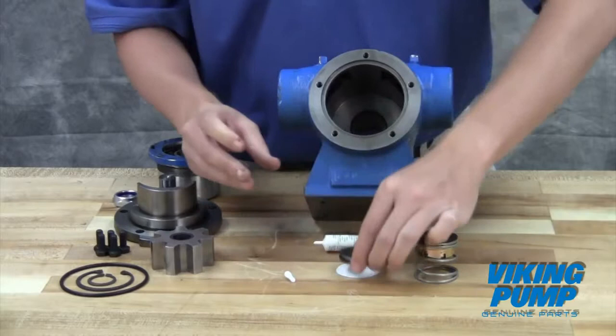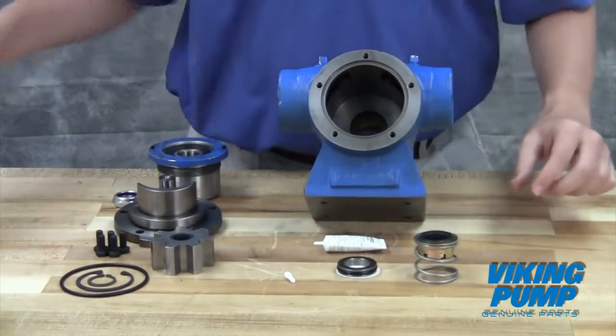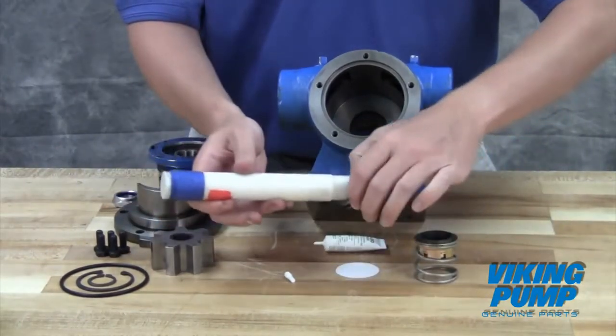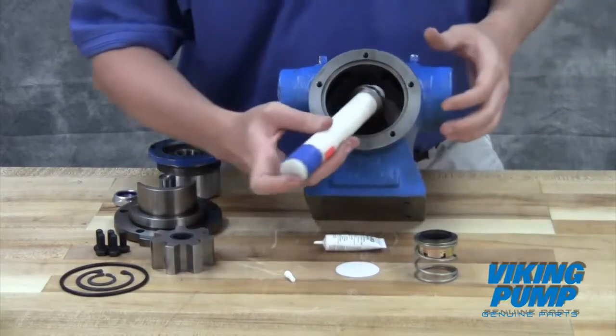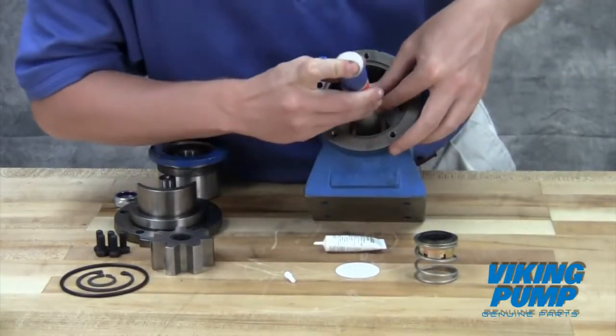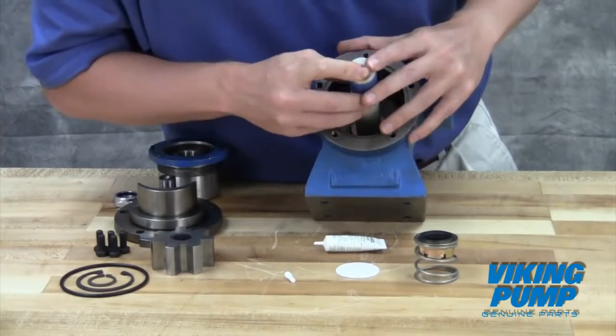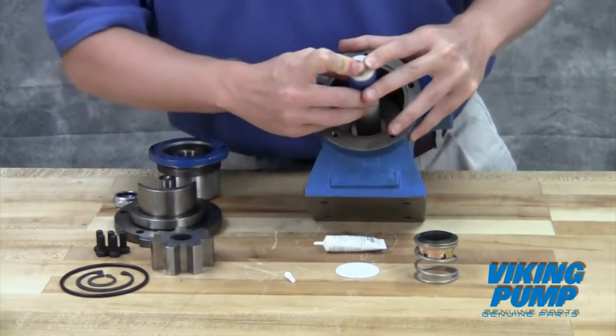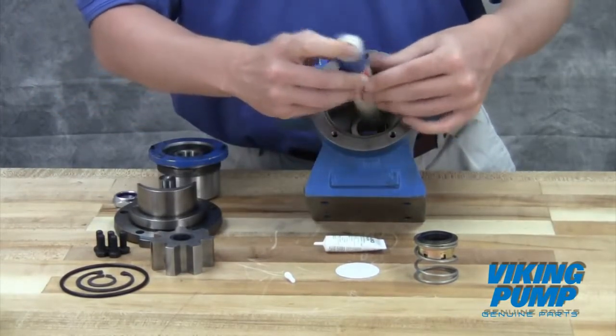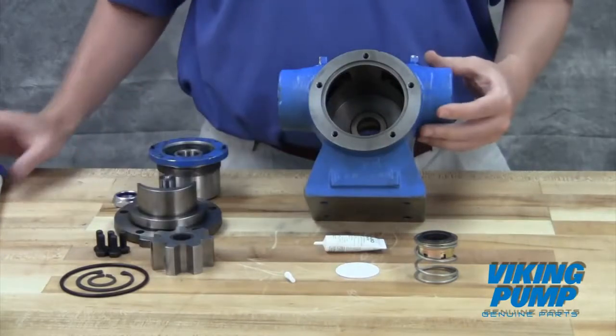Press the seal seat into the bore using only your thumbs, touching only the outermost edge of the seat so as not to scratch the sealing face. A close-fitting dowel with a very slight step can also be used. Note that the wedge-type seal includes a small anti-rotation pin, which must be lined up with its hole prior to pressing in the seal face.